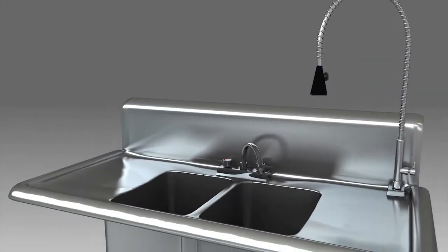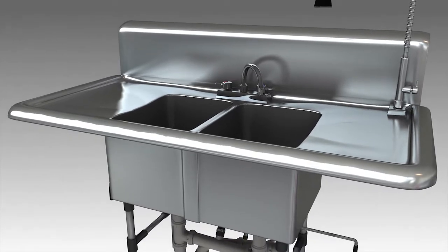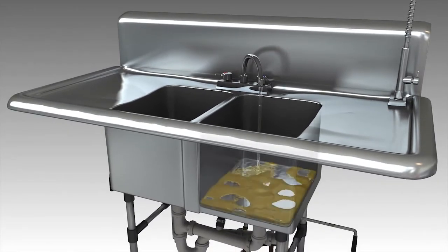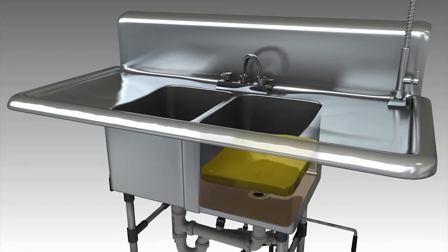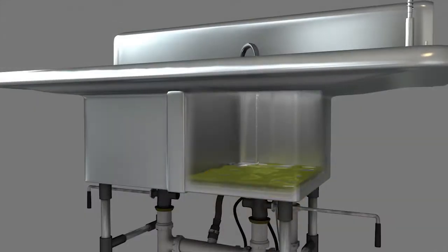Kitchen flows associated with grease often come in two forms: low flow discharge from pre-rinse or unstopped sink where flow rates rarely exceed 5 gallons per minute, and impounded flows where sinks are filled and then dumped all at once resulting in much higher flow rates.